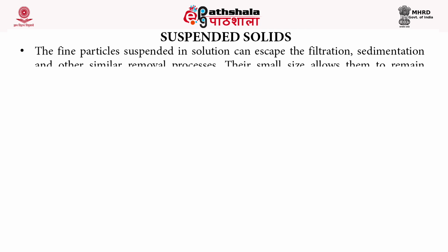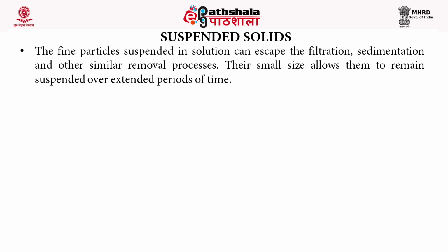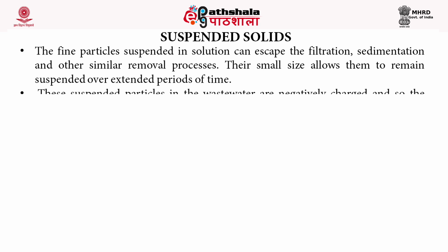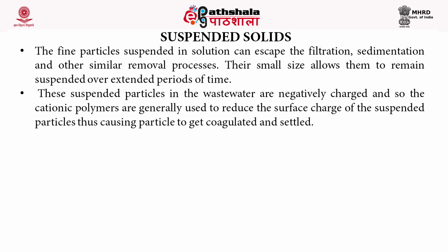Next, for the removal of suspended solids in the water, the fine particles, because of their small size, escape filtration, sedimentation and other similar removal processes. Their small size allows them to remain suspended over extended periods of time. These suspended particles in the wastewater are negatively charged, so cationic polymers are generally used to reduce the surface charge of these suspended particles, causing them to coagulate and settle.